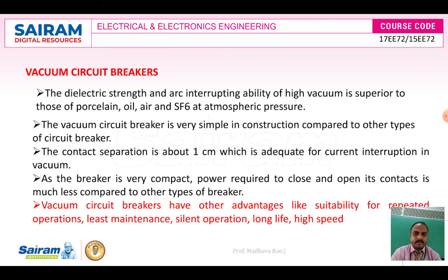So the vacuum circuit breaker. Vacuum has good dielectric strength and is a good arc interrupting medium, and the ability of high vacuum is superior to those of porcelain, air, oil, and SF6 at atmospheric pressure. So these are the things compared to oil, air, SF6. Vacuum has good dielectric strength and high capability of arc interruption. That's why vacuum circuit breakers are more popular.